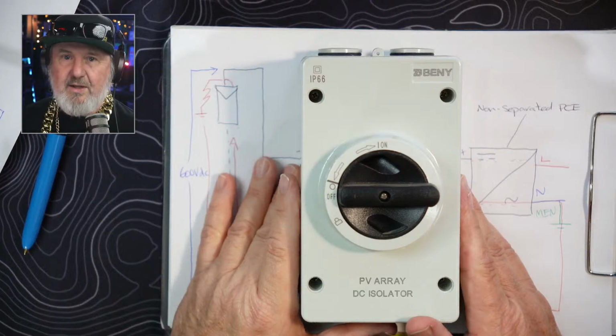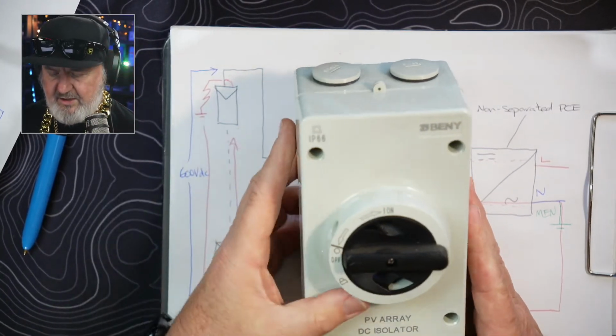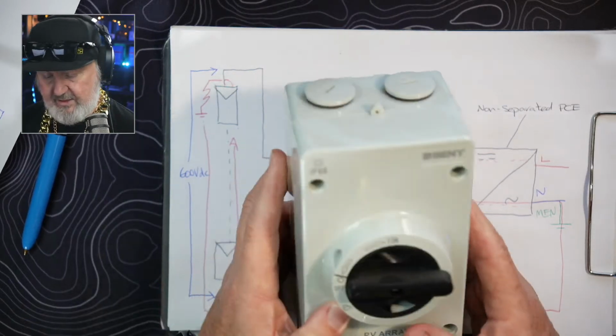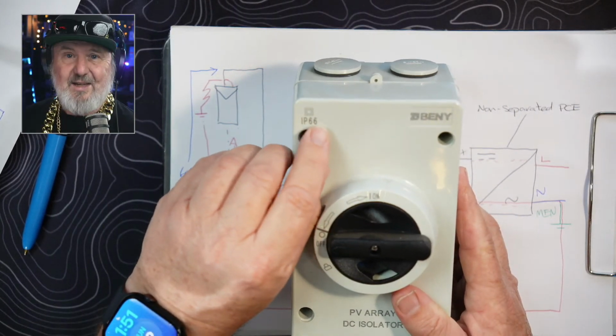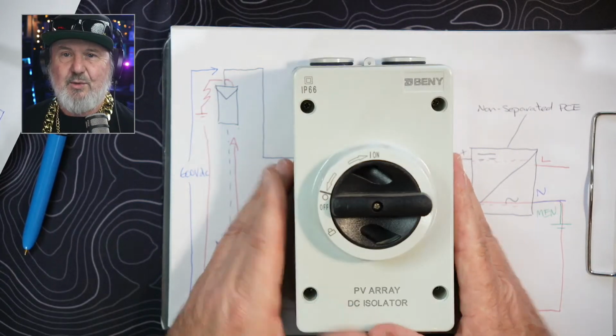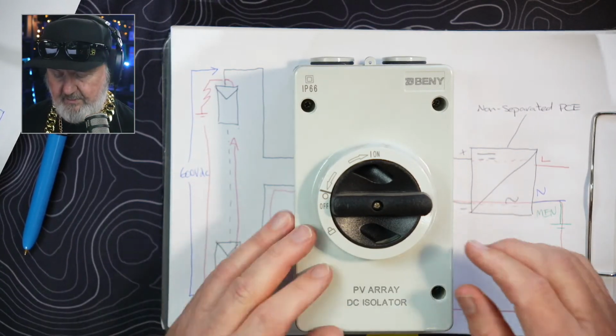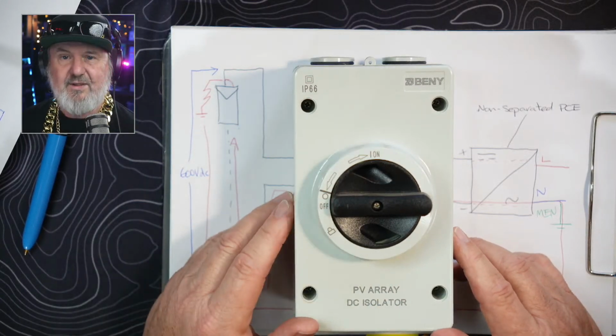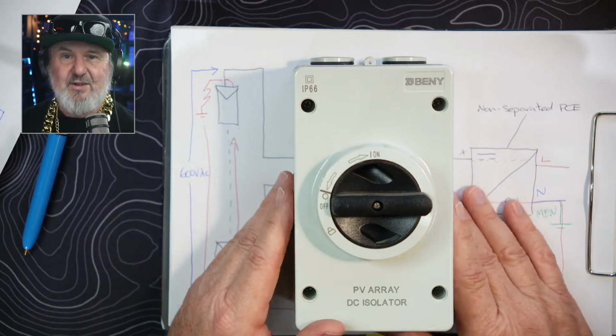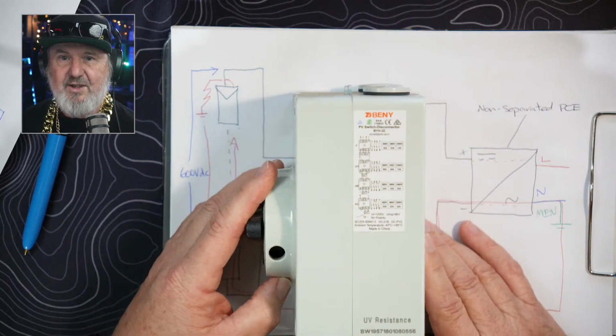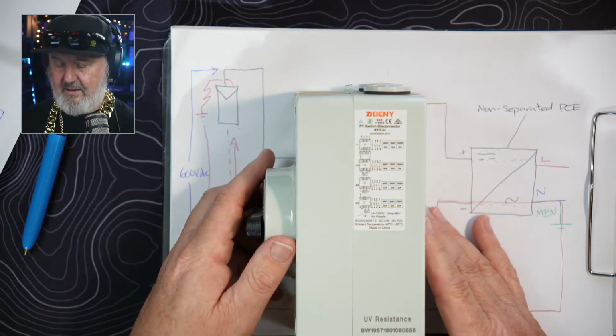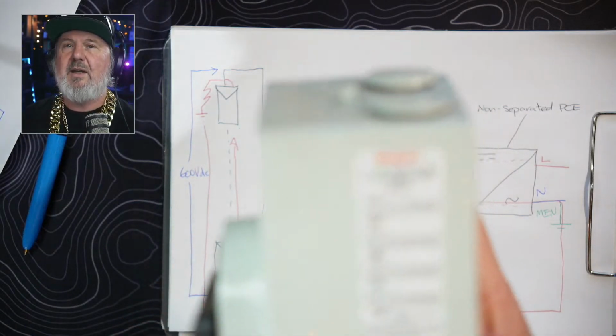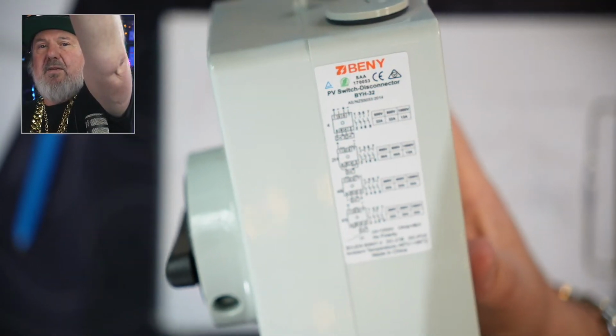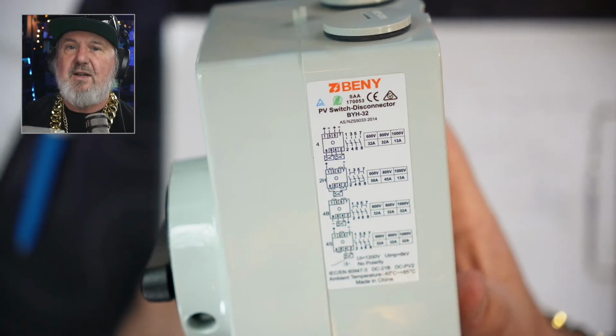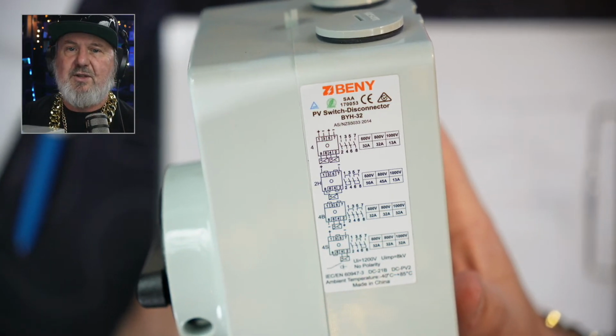And it meets a bunch of requirements. So, actually, this is the older one. And normally it has IP66NW written on there, the newer versions, because we introduced the no water requirement. But a bunch of things. You've got to have marked on and off on the unit. So markings are actually a mandatory requirement. And on the side here, let me make this a bit bigger and zoom in for you. There we go. Very helpfully on the side, they show some different configurations and voltage ratings.